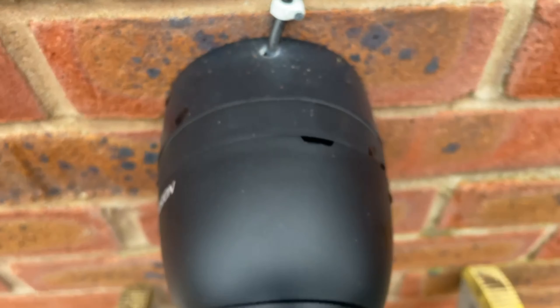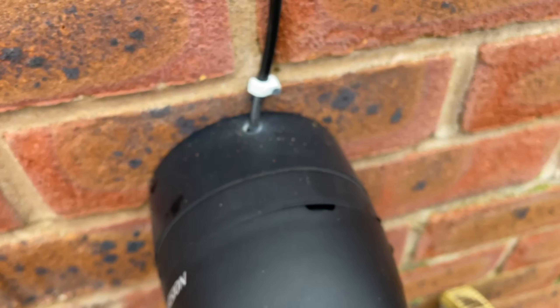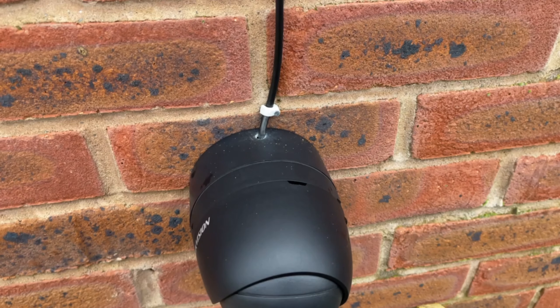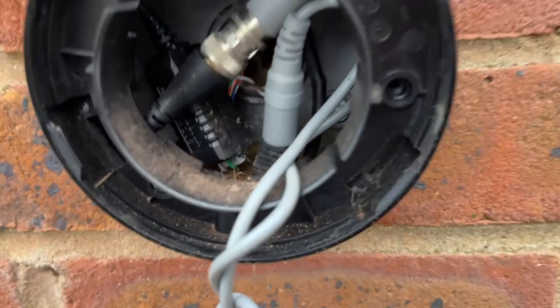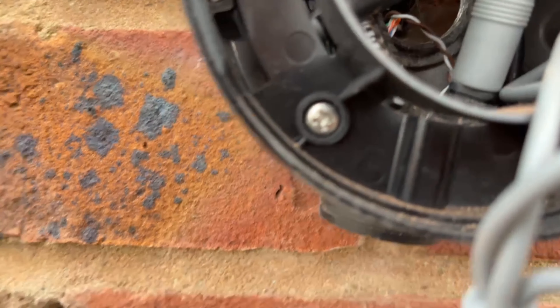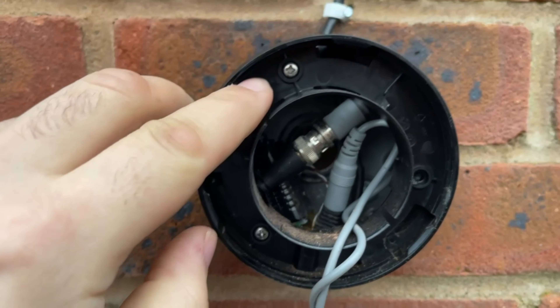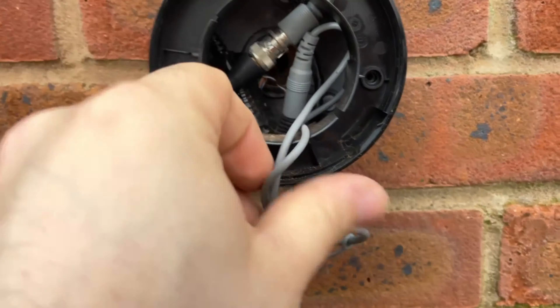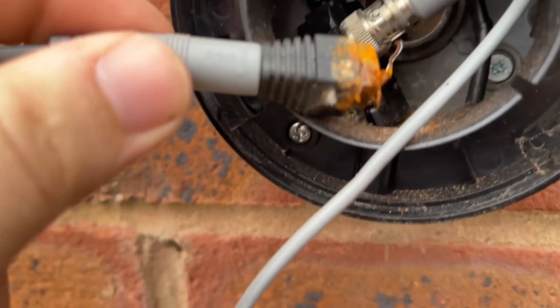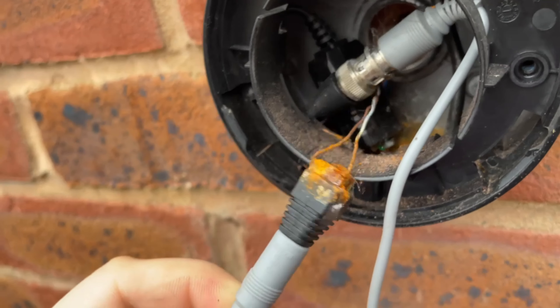There's a nice IP-rated hole in the back box — beautiful. Camera off now. Straight away you can see it's not looking too good — you can tell it's been flooded with water. And how many screws does he use on the camera? We've got one, two — one missing. Surprised he used two, to be fair. How are these people getting away with this stuff?